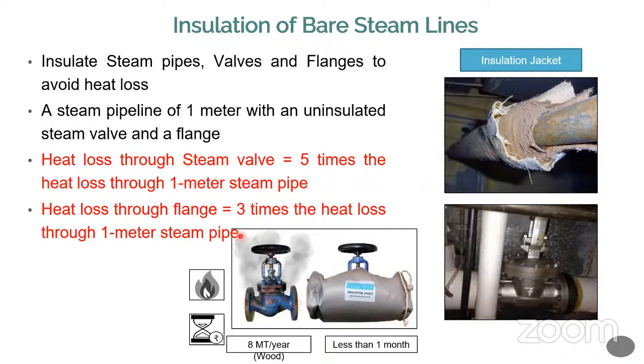There is another option now available in the industry. Instead of doing this type of insulation, they use a separate paint called TCC paint, thermoceramic coating paint, that can be painted on the valve or the flange, which does not allow the heat to escape. This paint can withstand 1200 to 1500 degrees. Of course, we are operating the steam at only 180 or 200 degrees. So if you put the paint on the valve or on the flange, automatically the outside temperature will be reduced by a minimum of 50 to a maximum of 100 degrees. That itself is going to be a good saving.